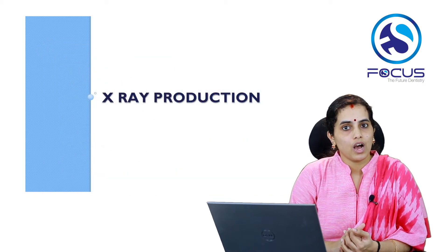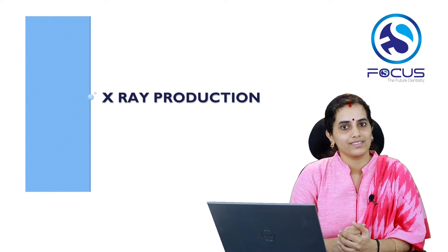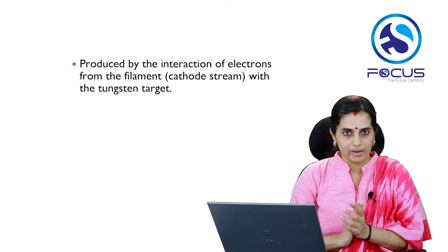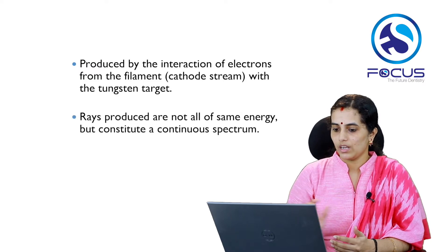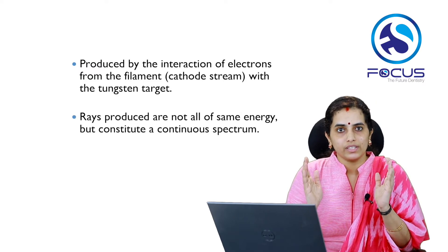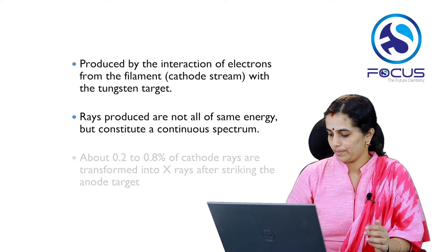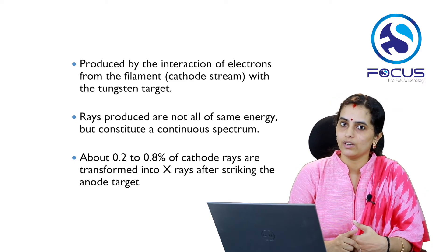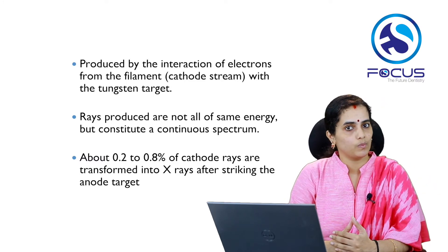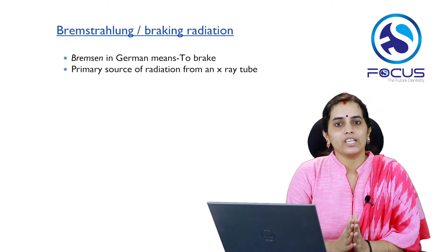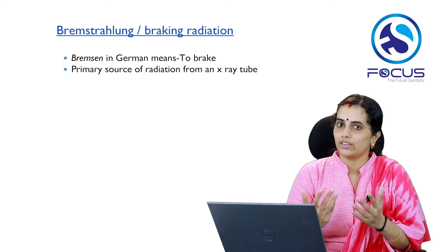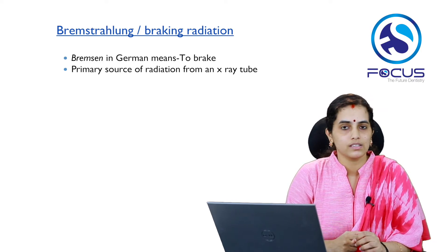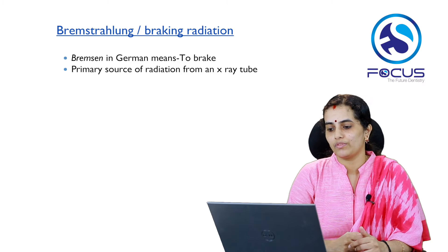X-rays are produced by the interaction of the electron beam from the tungsten filament with the tungsten target. Not all X-rays are of the same energy; we get a continuous spectrum of radiation. Only about 0.2 to 0.8% of the cathode rays are transformed into X-rays, while the remaining 99% is converted into heat. X-rays are of two types: Bremsstrahlung radiation and characteristic radiation. Bremsstrahlung, meaning 'braking radiation,' is the primary source of radiation from an X-ray tube.